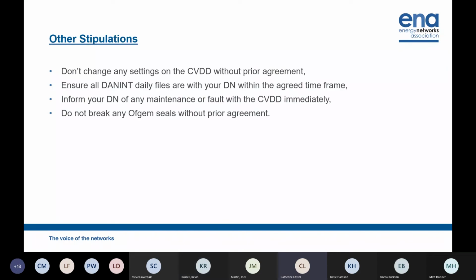Next one, please. Okay, there's a few other stipulations. These don't tend to cause too many Ofgem audit actions, but I thought they were worth mentioning. Please don't do any changes in the Danint software or your controller software without prior agreement from either your DN or from Ofgem. Ensure that all the Danint daily files that are created with all your end of day values are with your DN within the agreed time frame. I think quite a lot of sites are set up with automatic collection, but if this fails, then these need to be picked up manually and emailed or sent to your DN so that we can get them.